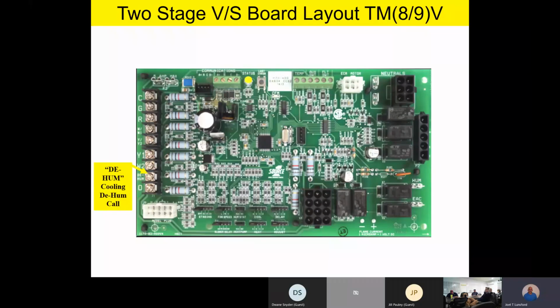Now, this is a little bit interesting because this is a variable speed product. We have what we call a dehum cooling terminal. This is a dehumidification terminal that we can use in the cooling mode of operation. How this works is if you've got a humidistat hooked up to the dehum and the R terminal, in other words, you just put a humidistat between R and dehum, what will happen in the cooling mode of operation, if it's humid in the house, the contacts will be open on a rise of humidity, and it'll actually slow the indoor fan down in the cooling mode of operation to provide dehumidification for cooling.